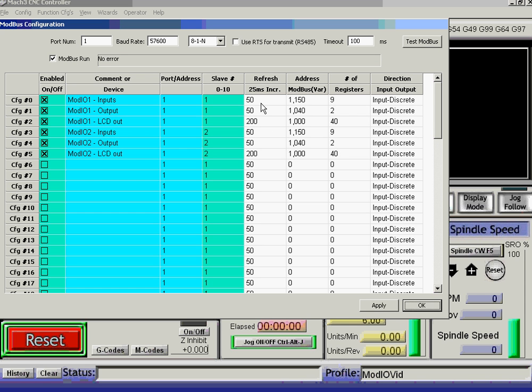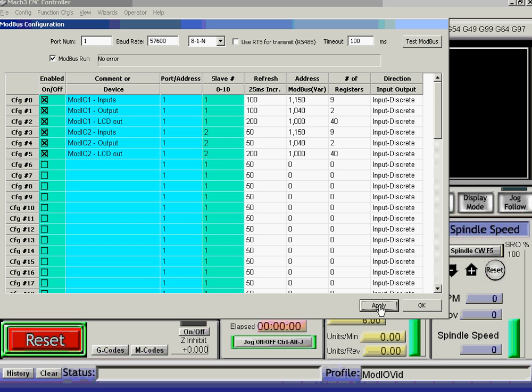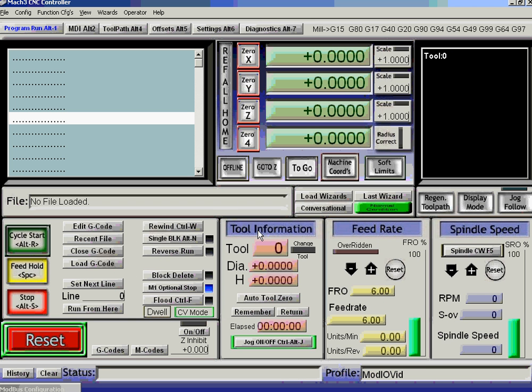Now, you can change the refresh rate in here by editing it and applying it. Supposing we decided that in fact it was perfectly alright, because we hadn't got any MPGs or anything fast to change the newer ModIO, the first one, to 100. If we apply that, that will now affect the polling.